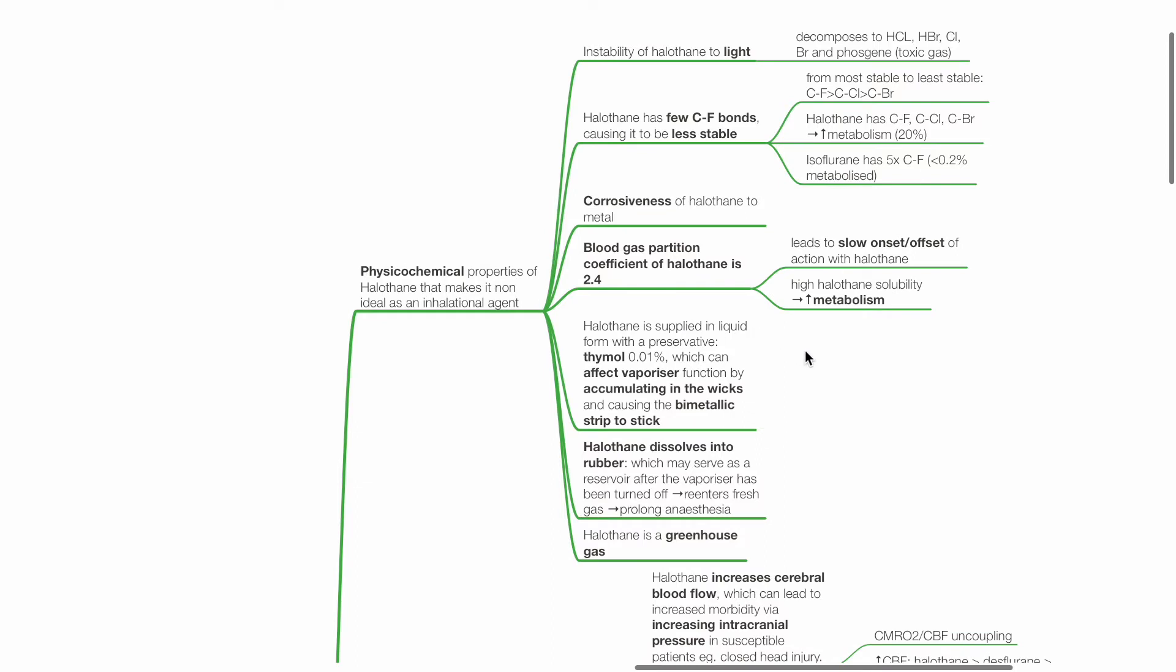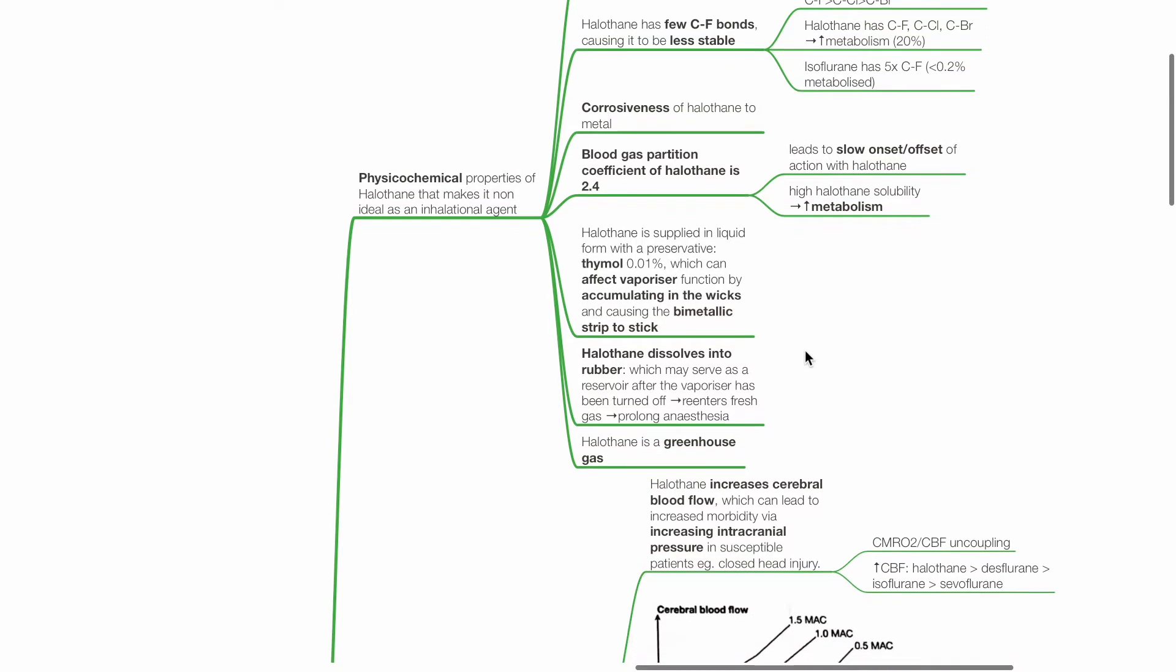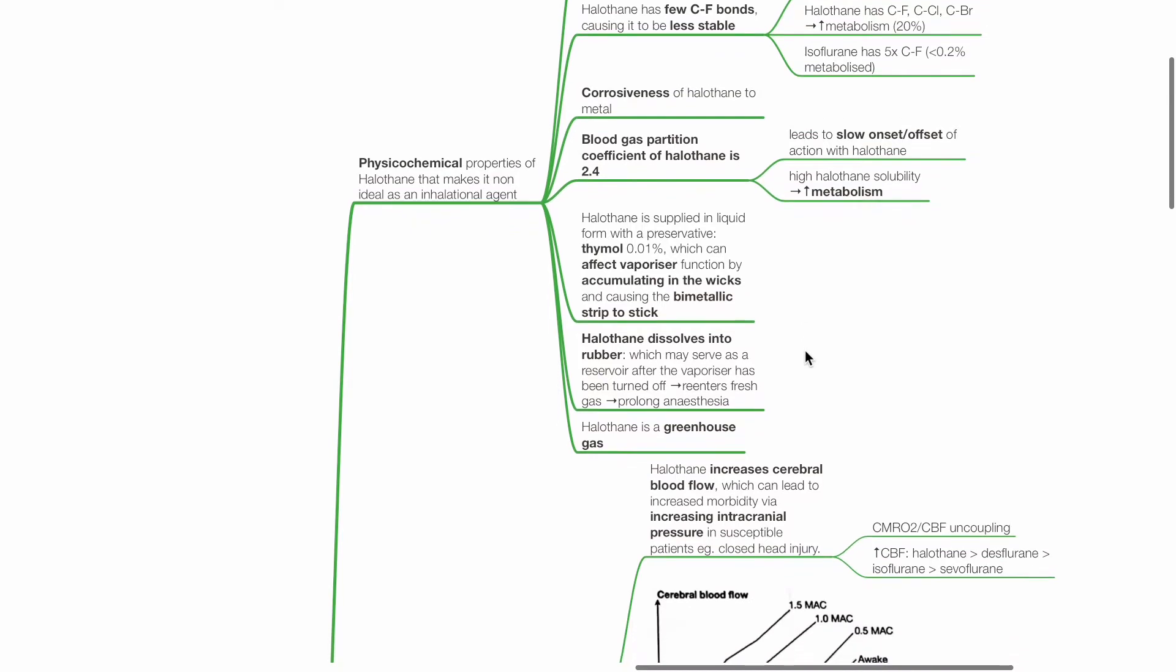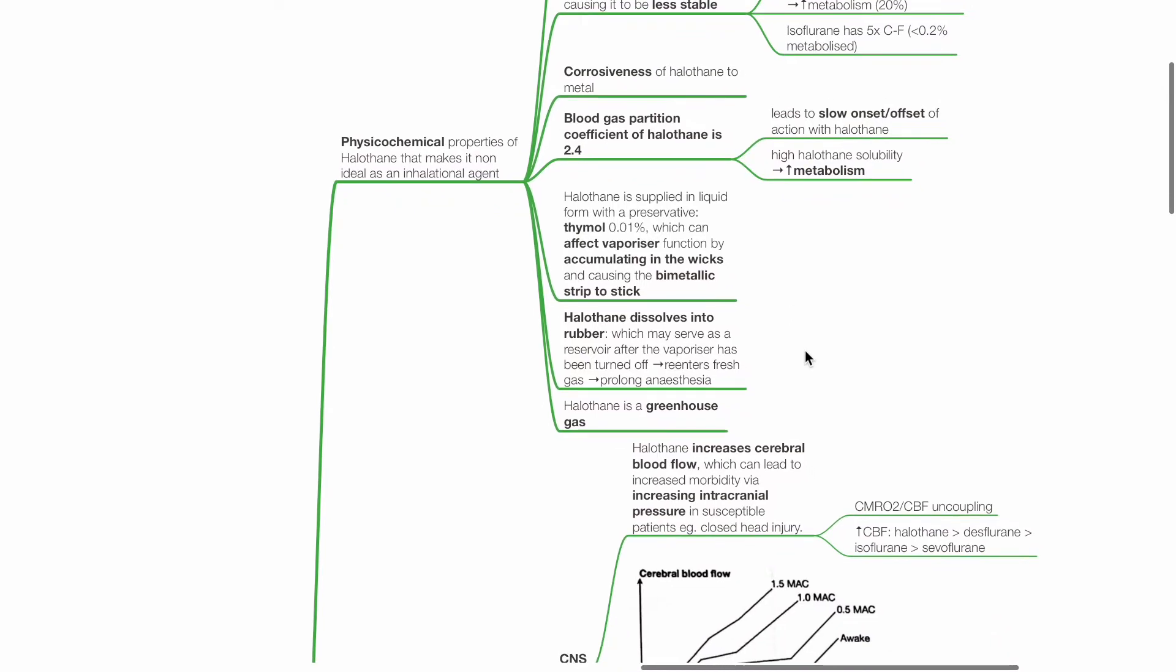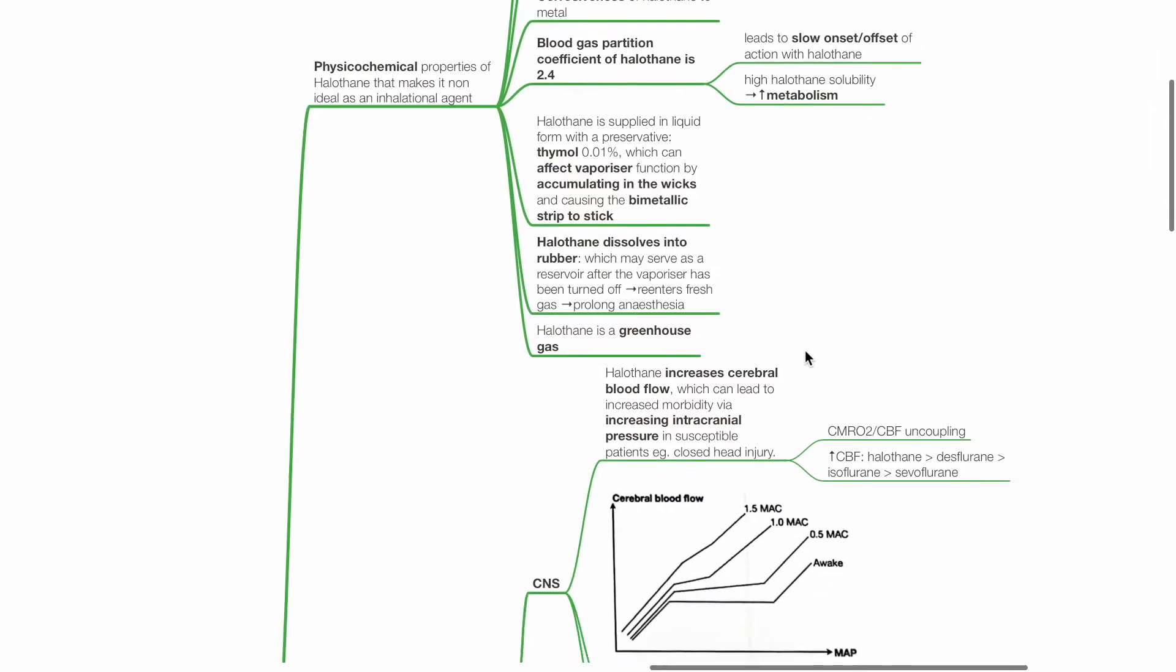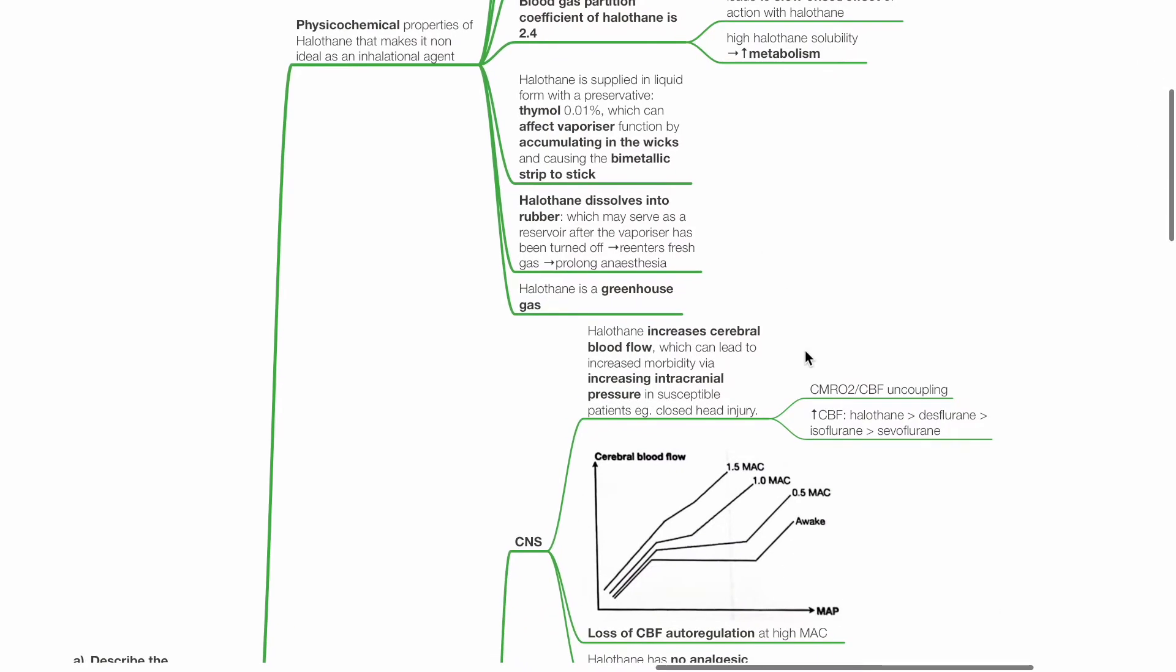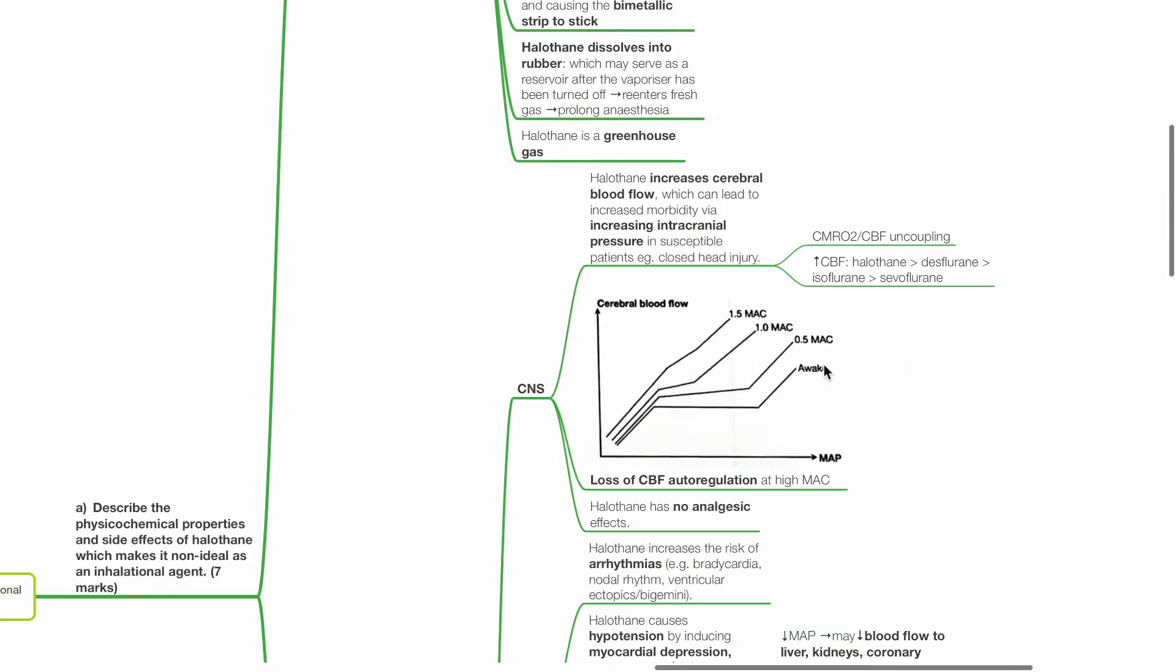Halothane is supplied in liquid form with a preservative, thymol, 0.01%, which can affect vaporizer function by accumulating in the wicks and causing the bimetallic strip to stick. Halothane dissolves into rubber as well, which may serve as a reservoir after the vaporizer has been turned off. Halothane then re-enters the fresh gas and prolongs anesthesia. Lastly, halothane is a greenhouse gas.